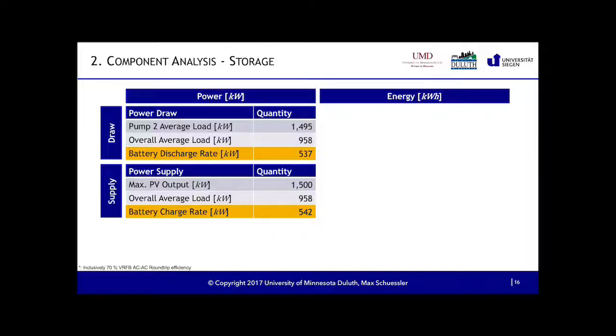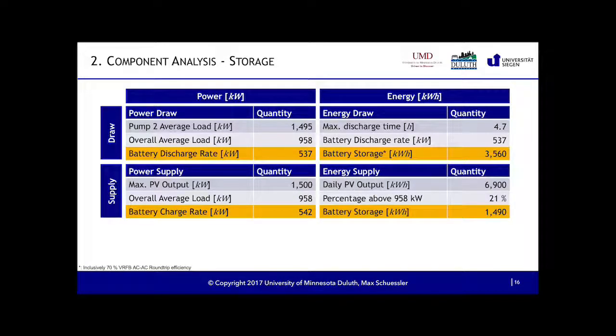I looked into, okay, now I know what I want, now I know what the load character looks like, and now I want to know which size I actually need for that battery. And I can either look at what the PV system supplies to the battery, or what my pumps draw from the battery. So I have a draw or a supply side. And I just did some math, and hopefully some good math about it, and I came up that for the power rating of the battery, when we look at what the pumps actually need, we need 540 kW.